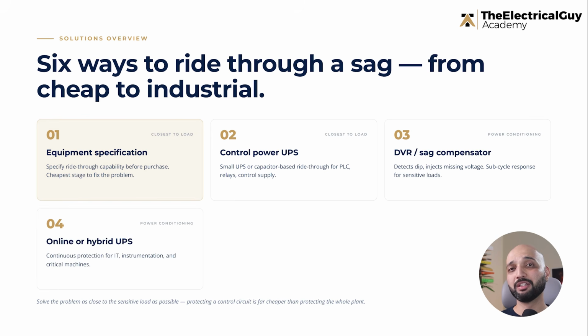The fourth solution is UPS for larger loads. An online UPS continuously supplies the load through the rectifier and inverter. It provides strong protection against sags and interruptions, but it has losses, cost, battery maintenance, and space requirements. A standby UPS normally supplies the load from the main line and transfers to the inverter during disturbances. It is cheaper, but transfer time becomes important. If the load cannot tolerate even a few milliseconds, a standby UPS may not be good enough.